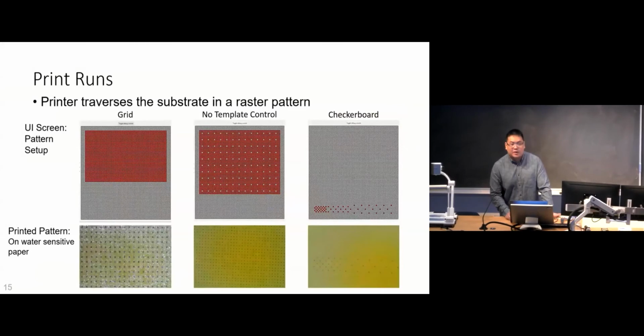And this is to account for any rotation in the chip, and it is compensated during the print run. After alignment, a print area is defined and it is highlighted by the red markers in this UI. The instrument will traverse this area in a raster pattern, and different print patterns can be defined other than a regular grid as shown on the left. Other patterns it can define is a no template control pattern, which periodically skips a well. This can be used to assess any background ambient genomic signal that may be present by sequencing wells that do not have anything dispensed into them.